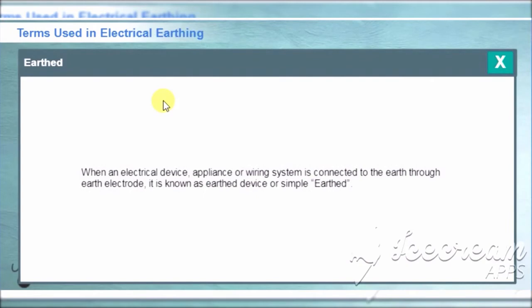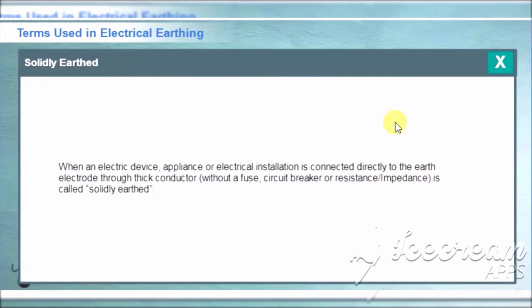Earthed. When an electrical device, appliance, or wiring system is connected to the earth through earth electrode, it is known as earthed device or simply earthed. Solidly earthed. When an electrical device, appliance, or electrical installation is connected directly to the earth electrode through thick conductor without a fuse, circuit breaker, or resistance or impedance, it is called solidly earthed.